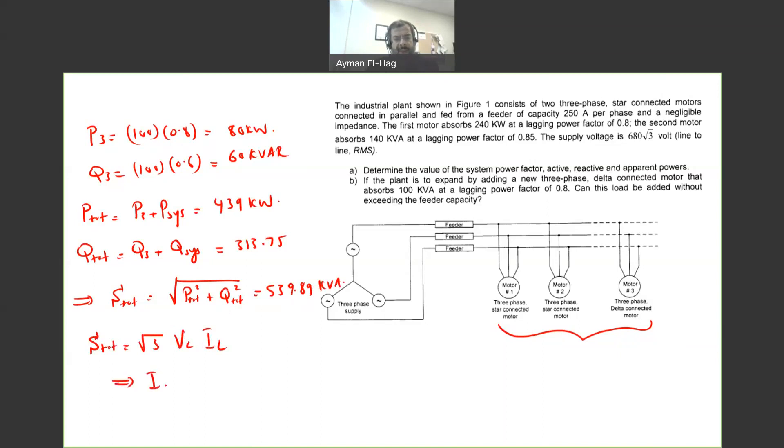So this is IL total equal to the S total divided by root 3 V line. So this is equal to 539.89 times 10 to the power 3 divided by root 3. Now the line-to-line voltage was given to us as 680 times root 3. So it's root 3 times 680, and when you calculate this, you will find the current is 264.5 amp, which is more than the 250 amp, the capacity.